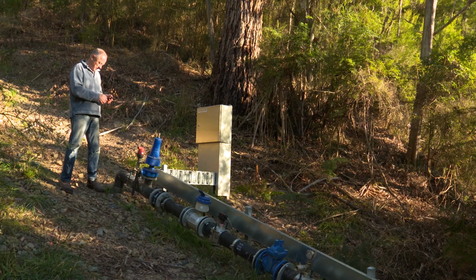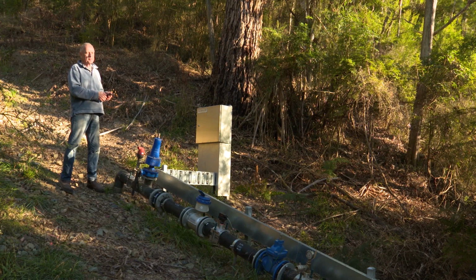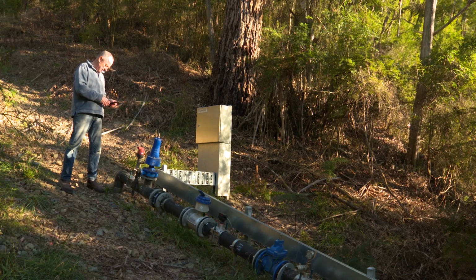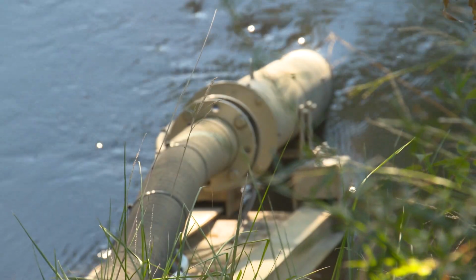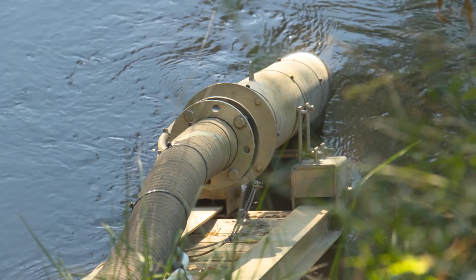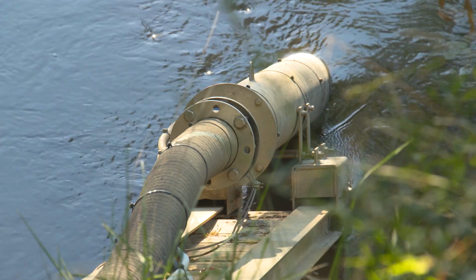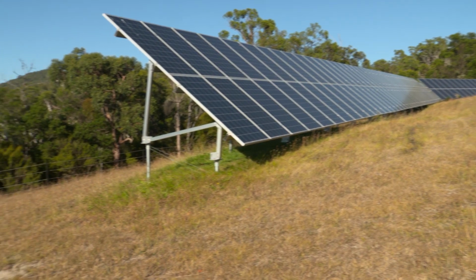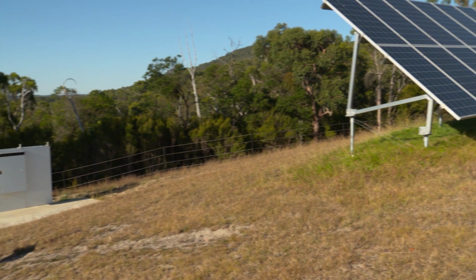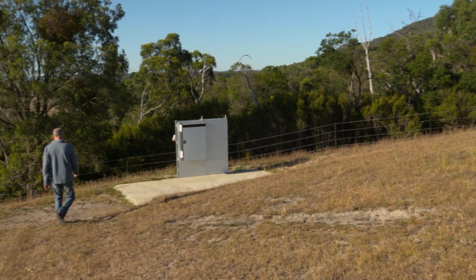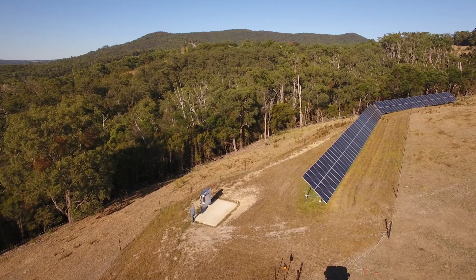What we came up with was a 22 kilowatt high efficiency permanent magnetic motor. One thing very interesting with this job is that the pump is actually so far away from the solar array, that's quite a problem. Most pumps like that with solar need to be very close to where the variable speed drive is.